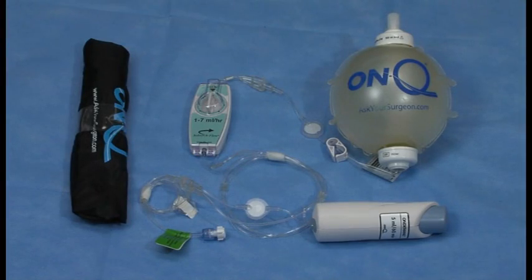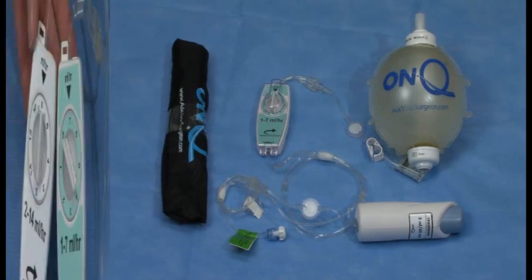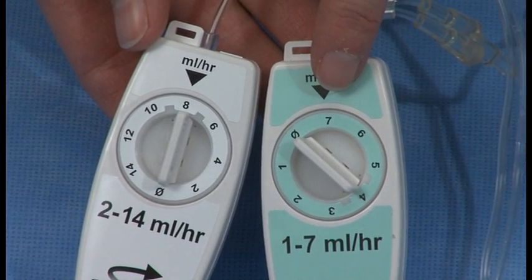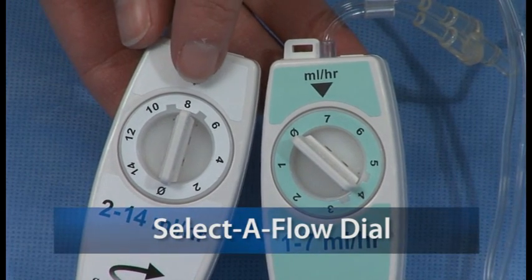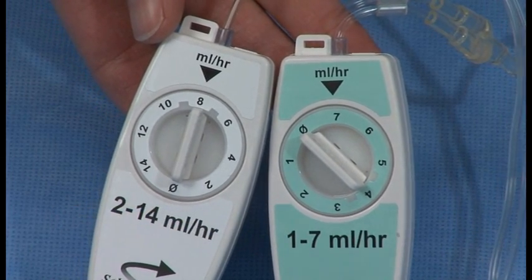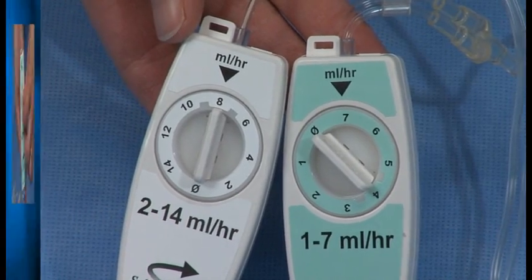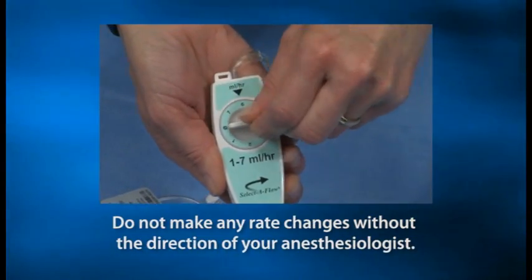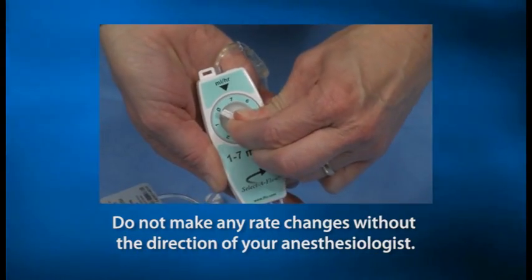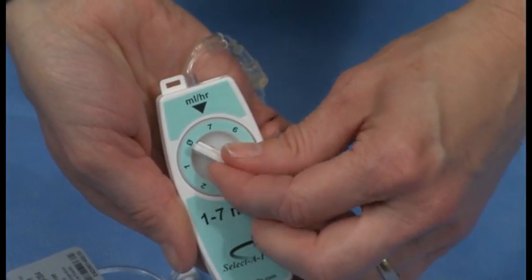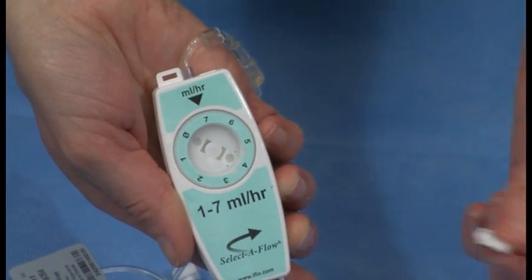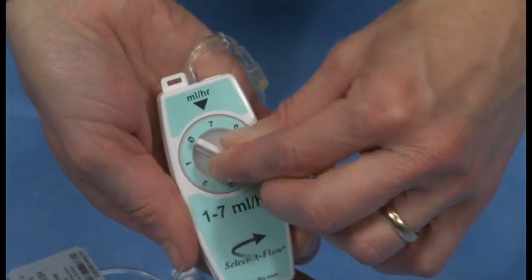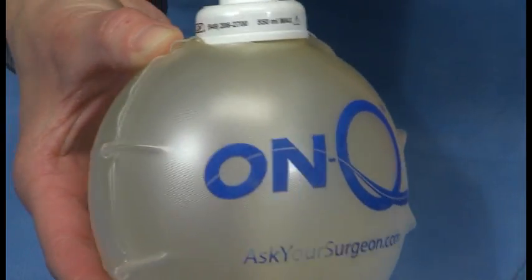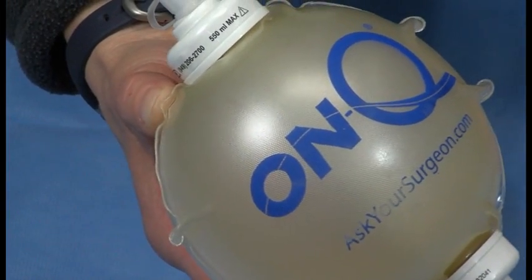Your pressurized, ON-Q infusion pump delivers local anesthetic continuously at a programmed rate determined by your anesthesiologist. A black arrow on the Select-A-Flow dial points to the number that corresponds to the rate of your infusion. The rate is programmed in milliliters per hour. Do not make any rate changes without the direction of your anesthesiologist. The rate changing key is removable. If it comes off, it can be easily inserted back into place. The pump is pressurized and does not need elevation to function properly.